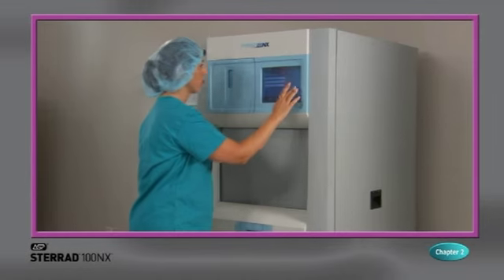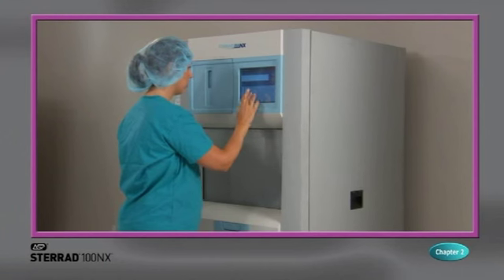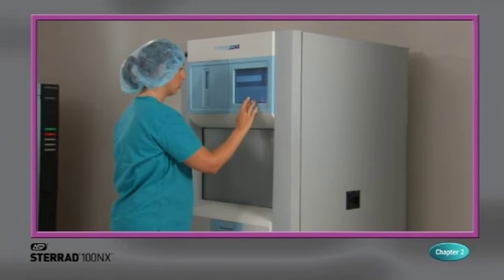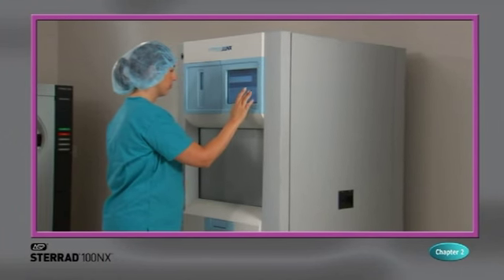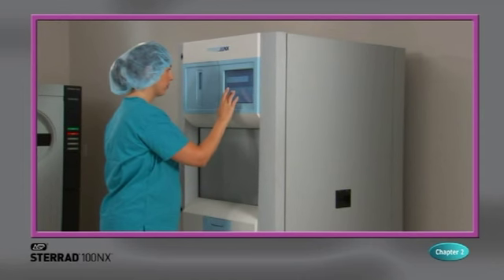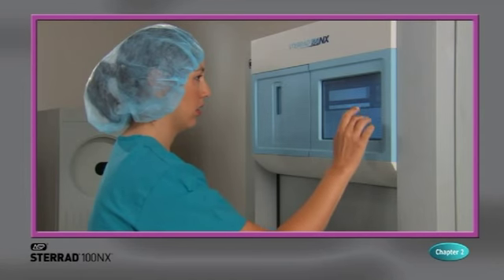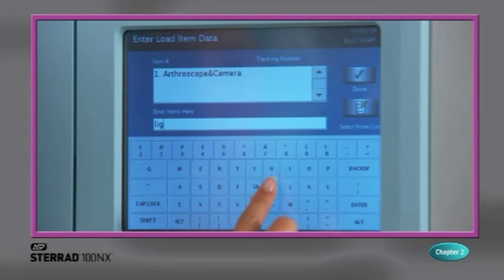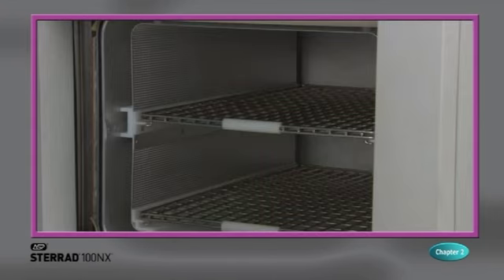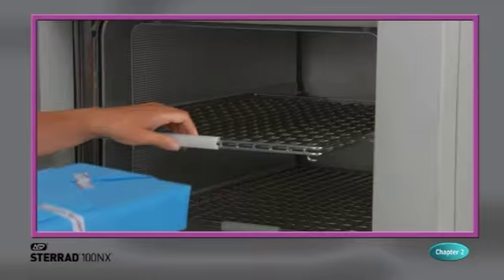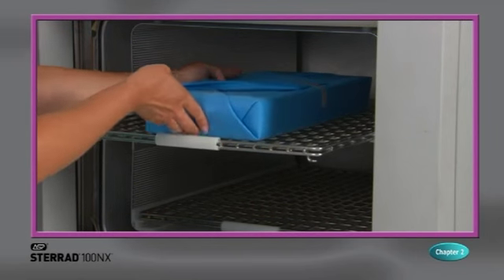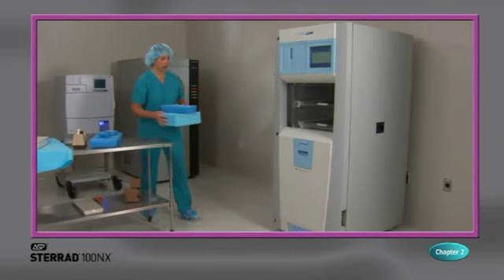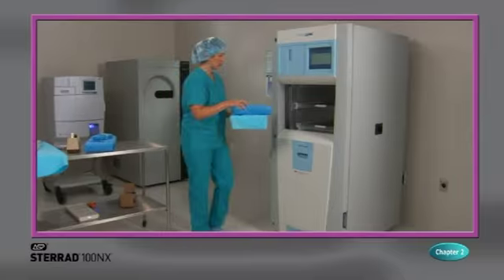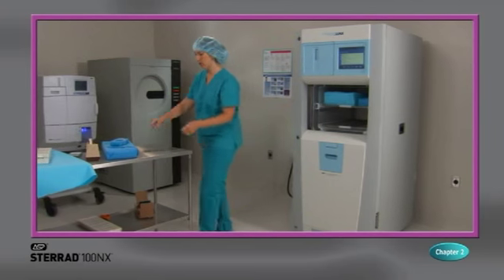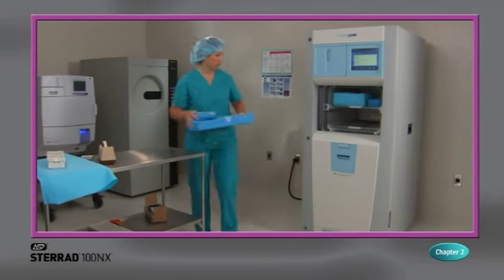The Sterrad 100NX sterilization system is a general-purpose, low-temperature sterilizer that features ASP's next-generation technology to inactivate microorganisms on a broad range of medical devices and surgical instruments. This sterilizer offers an effective, safe, fast, and easy-to-use sterilization method. When used as directed by the instructions in the user's guide, the Sterrad 100NX sterilization system will sterilize both metal and non-metal medical devices at low temperatures.